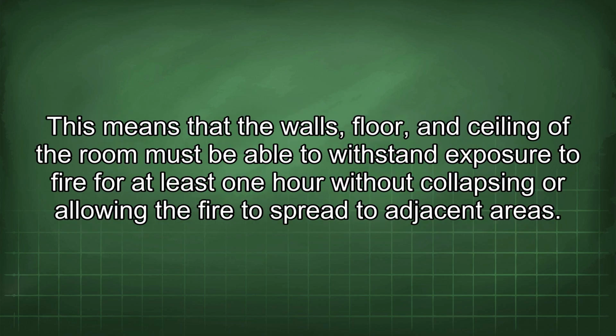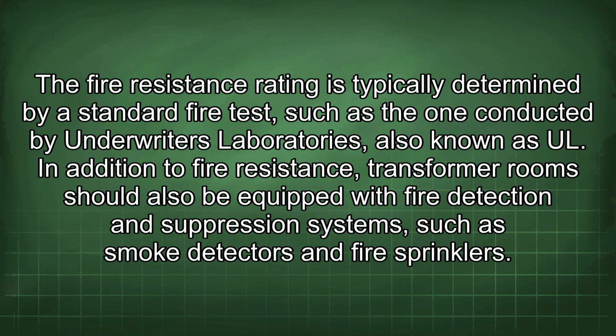This means that the walls, floor, and ceiling of the room must be able to withstand exposure to fire for at least one hour without collapsing or allowing the fire to spread to adjacent areas. The fire resistance rating is typically determined by a standard fire test, such as the one conducted by Underwriters Laboratories, also known as UL. In addition to fire resistance, transformer rooms should also be equipped with fire detection and suppression systems such as smoke detectors and fire sprinklers.